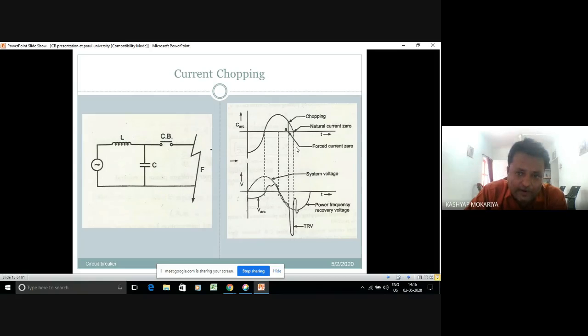So here what we are explaining is that if my current is chopped before the natural current zero, then definitely it will produce the TRV. It will produce a transient restriking voltage. So we have to find remedies for this. We have to solve the issues regarding current chopping in such type of breaker, and this is one of the methods.